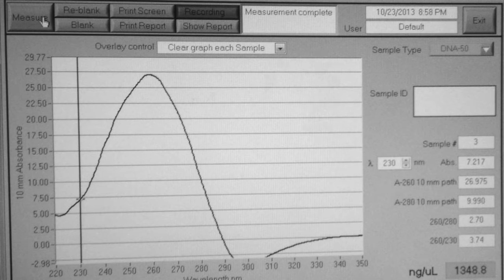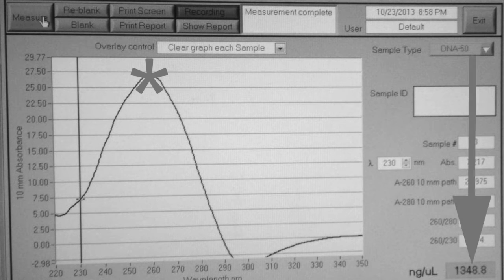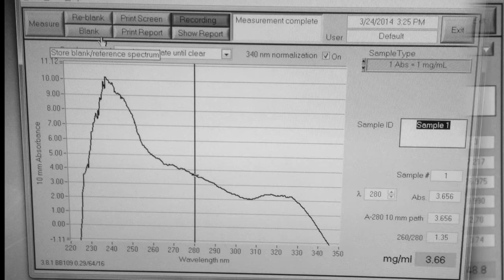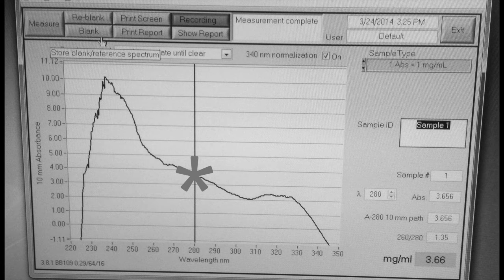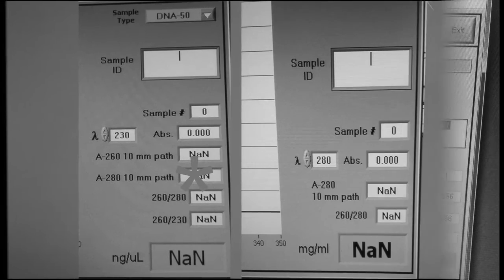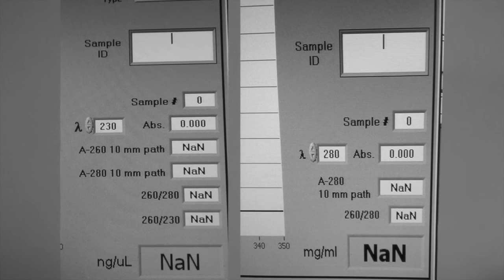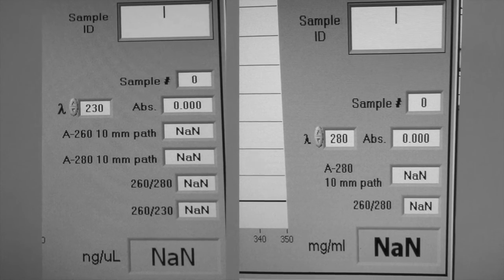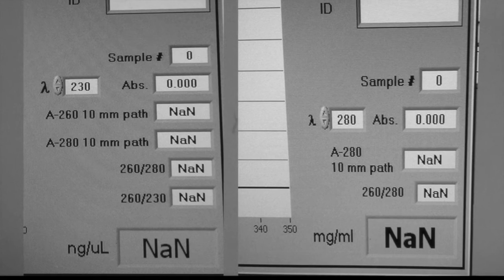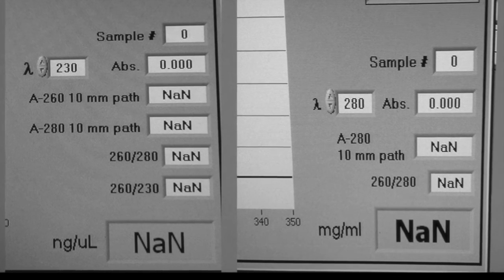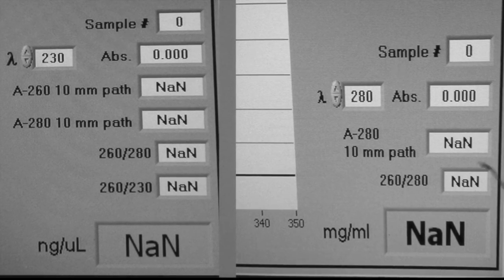Nucleic acids absorb highest at 260 nanometers, so the machine multiplies that measurement by the right conversion factor and the dilution of the sample to give the concentration in nanograms per microliter. Proteins absorb best at 280 nanometers, so the machine plugs that measurement into the Beer-Lambert law to give the concentration in milligrams per milliliter. Both sample types are isolated from cells, so the ratio of absorbance at 260 and 280 tells the scientist if the nucleic acid is contaminated with protein or vice versa.